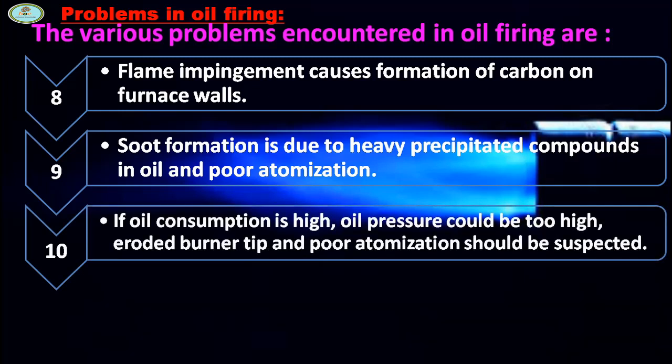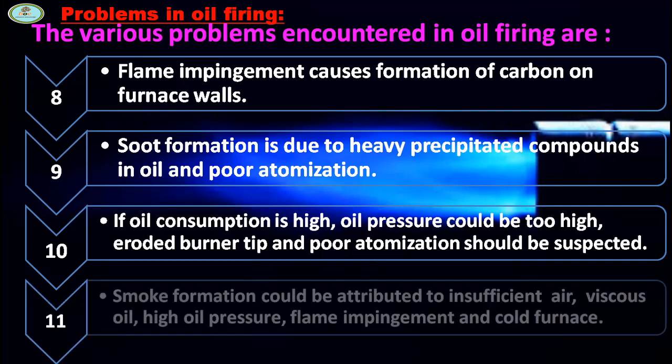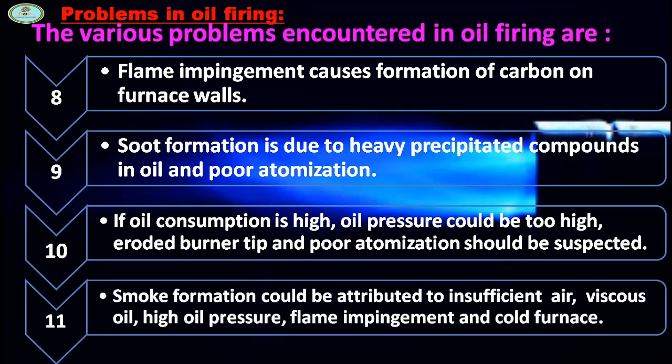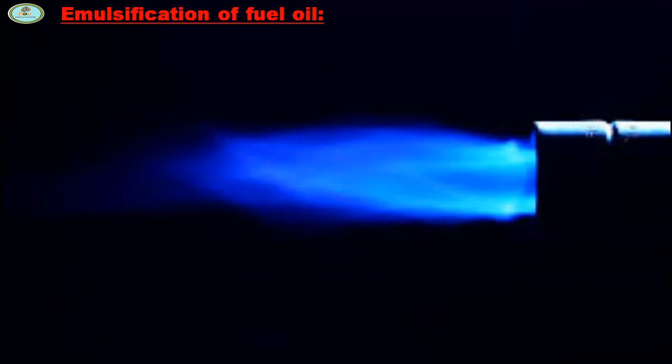If oil consumption is high, oil pressure could be too high, eroding the burner tip, and poor atomization should be suspected. Smoke formation could be attributed to insufficient air, viscous oil, high oil pressure, flame impingement, and cold furnace.